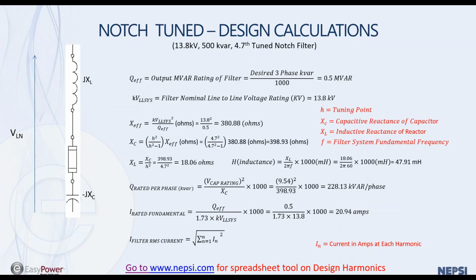But our general rule is to size the filter system such that the harmonic current is 50% of the fundamental. And then we rate the harmonic filter for 100%. So we give ourselves an additional 50% margin. And this is key, to make sure that you have margin in your design, because there are always unknowns that get you with these filter systems.